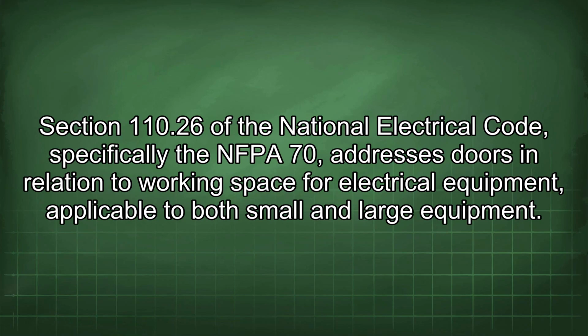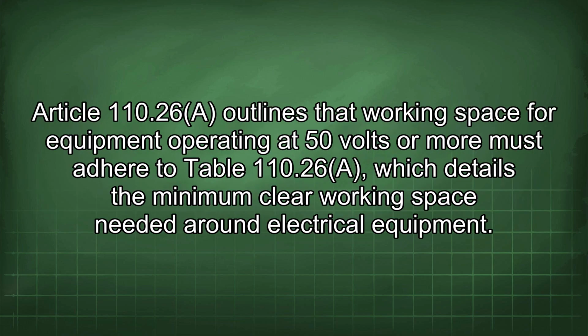Section 110.26 of the National Electrical Code, specifically NFPA 70, addresses doors in relation to working space for electrical equipment, applicable to both small and large equipment. Article 110.26 outlines that working space for equipment operating at 50 volts or more must adhere to Table 110.26(A), which details the minimum clear working space needed around electrical equipment.